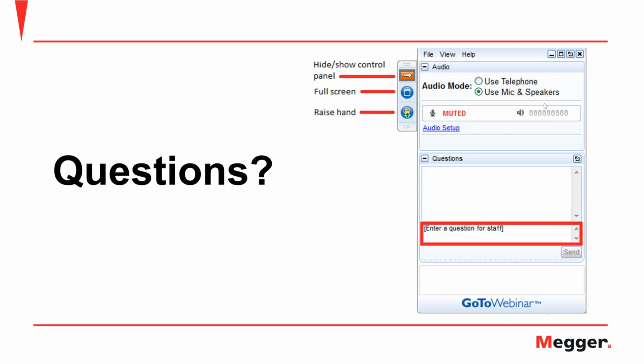This is not good. But your first test is going to break the ice, so to speak. And then subsequent tests can be done much more quickly once you have this idea of how big your grounding resistance sphere is. And you can certainly simplify your subsequent maintenance tests.